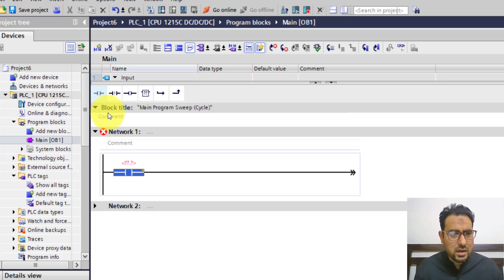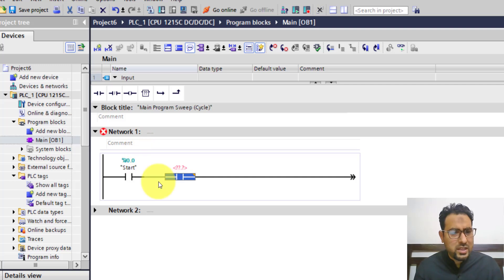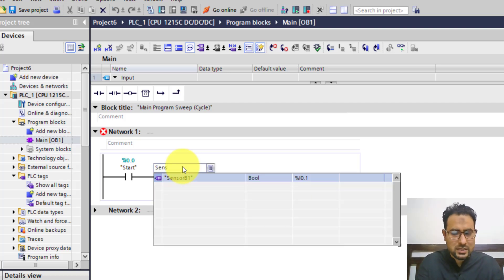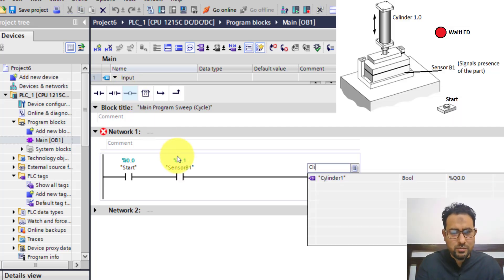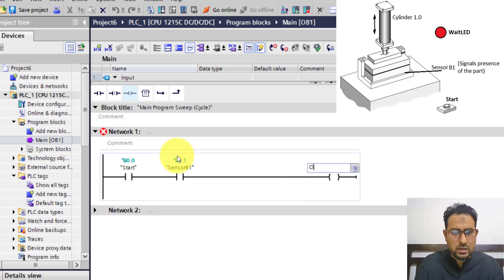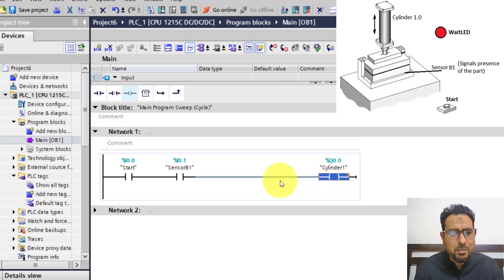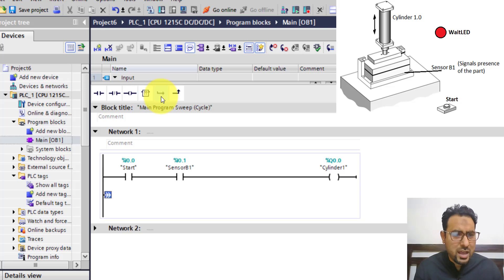The very first thing is I need a start button. I have inserted a start button and labelled it as start. Then if the part is present, only then the cylinder should extend. So in series I need the part presence sensor — sensor B1. The cylinder should extend as an output: cylinder 1. As long as the start button is pressed and sensor B1 detects the part, the cylinder remains extended. I'm going to latch the cylinder — we have already done this in the previous videos.